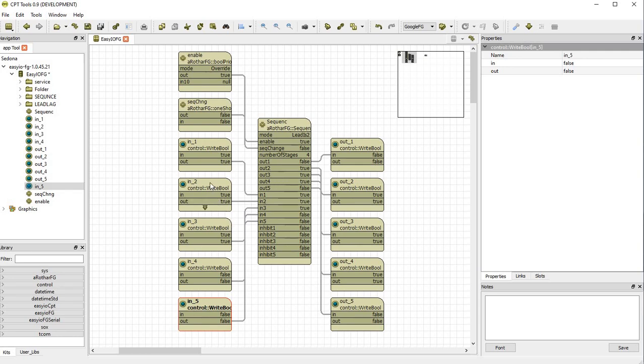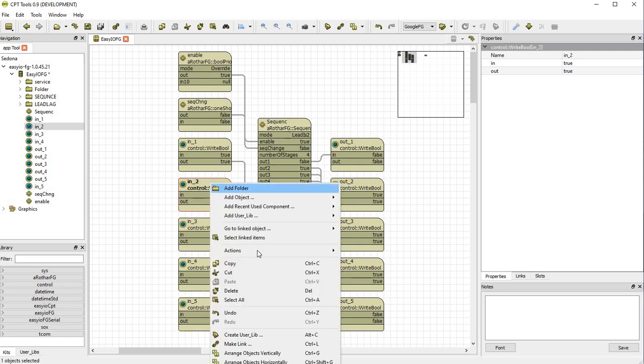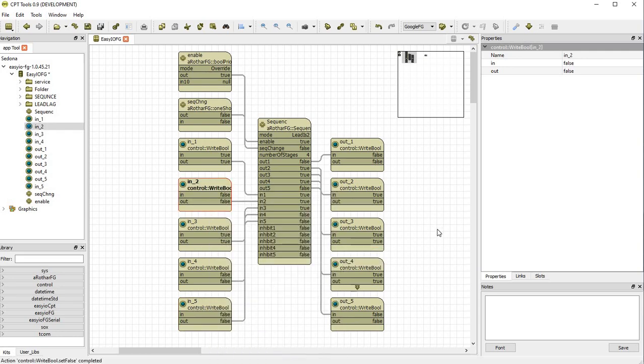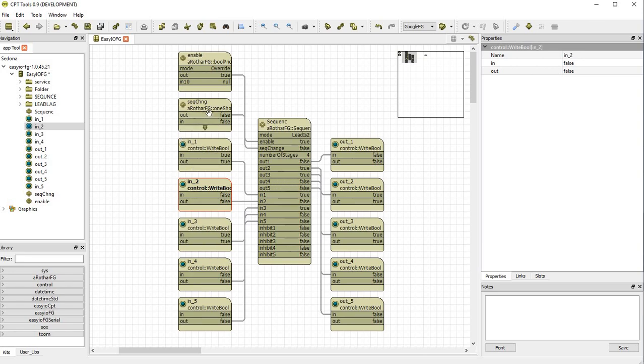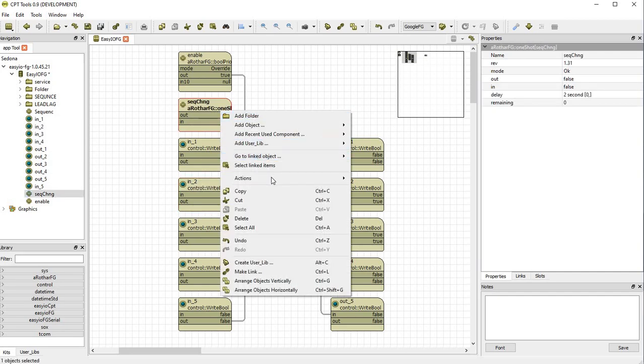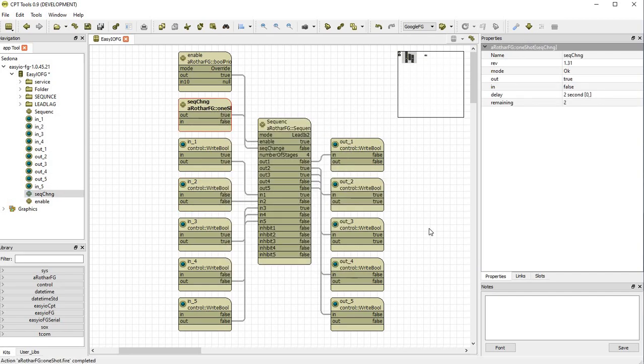So one will be the first one off because it is in effect the last unit to run. So if we turn off input two, output four will turn off because the inputs are requesting a number of stages to be on, not which stage to be on. If we ran a sequence change now, two would turn off and four will turn on. Two is off. Four is on. We still have two units operational.